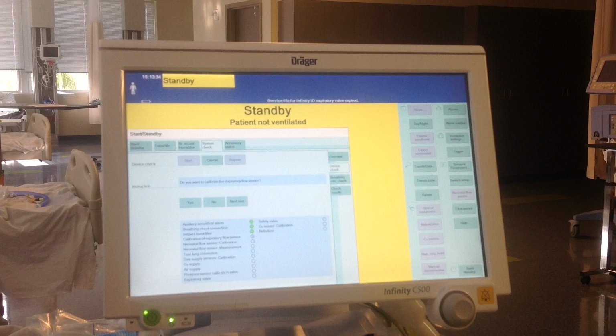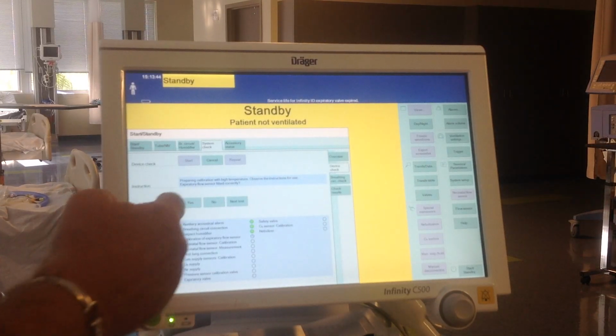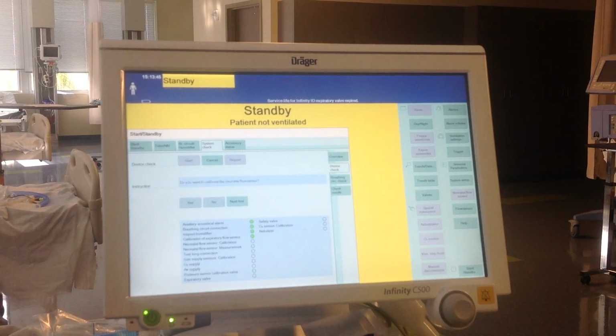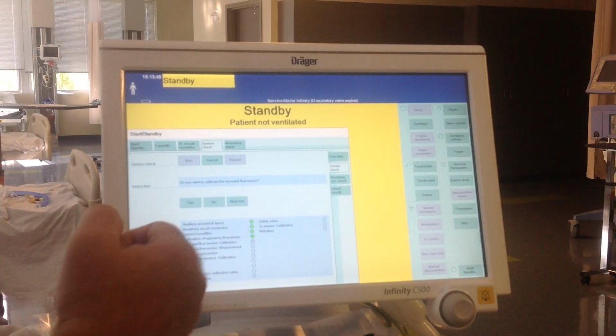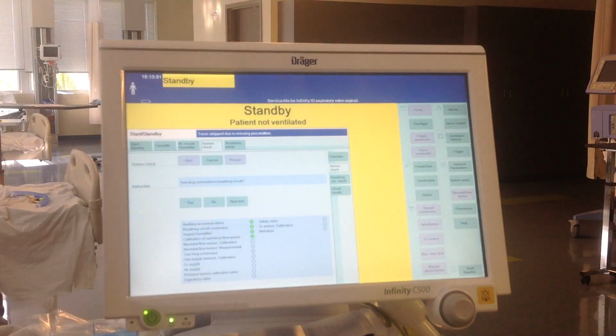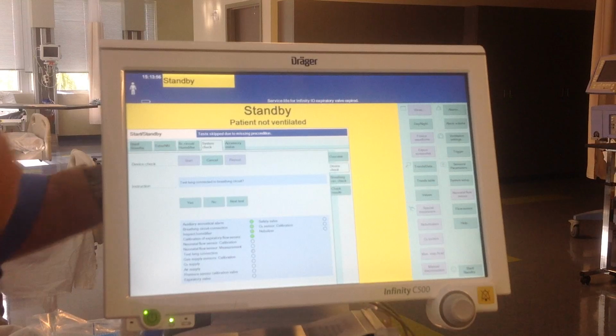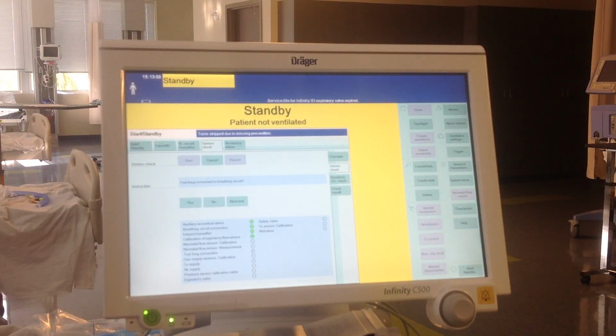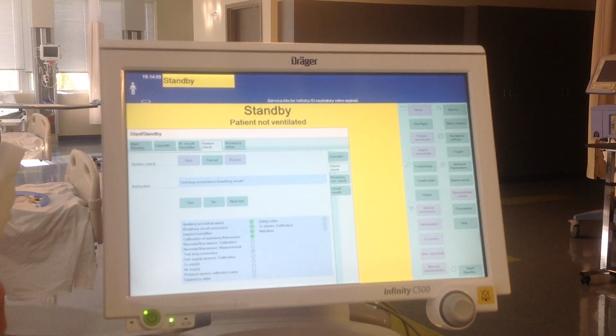Do you want to calibrate the expiratory flow sensor? Yes. Preparing calibration with high temperature. Observe the instructions for use. Expiratory flow sensor fitted correctly. Yes. Do you want to calibrate neonatal? No. You'll get to do that in the fall. Test lung connected to breathing circuit. So I'm going to take my elbow off. I'm not going to throw this away. And my test lung right here. Yes.